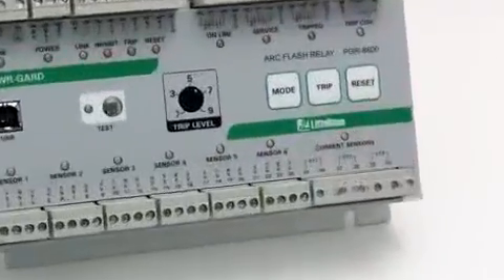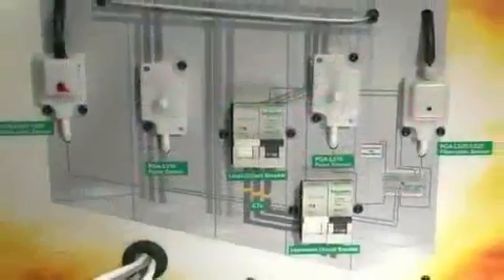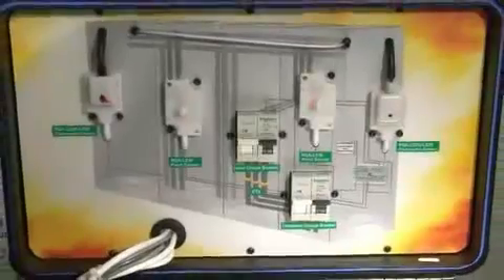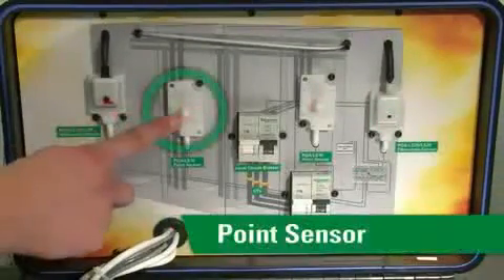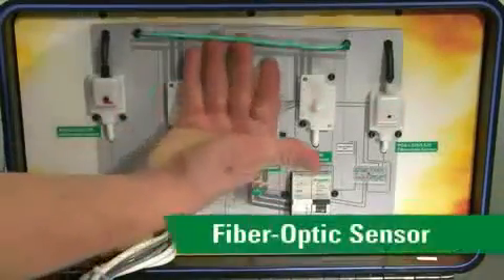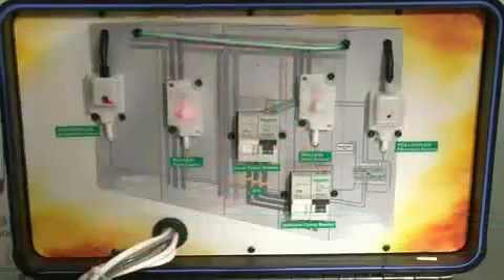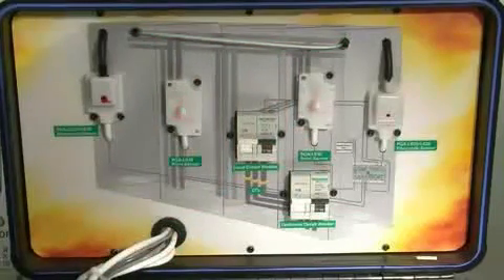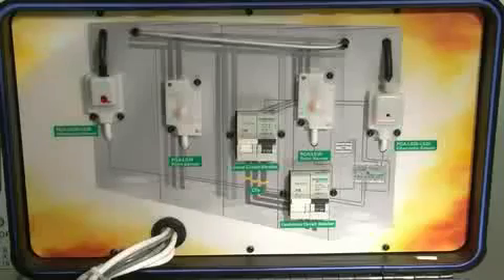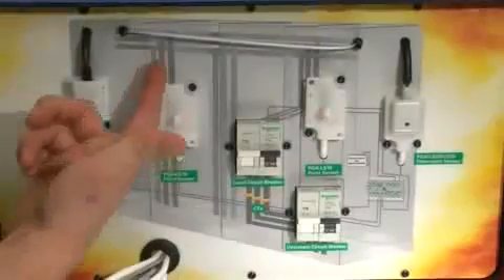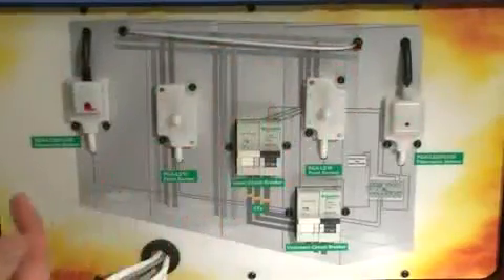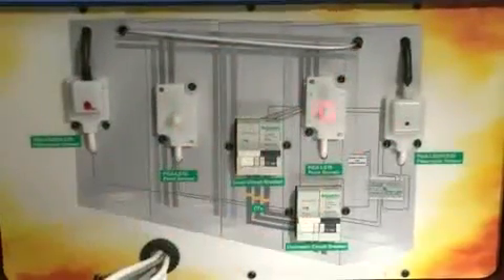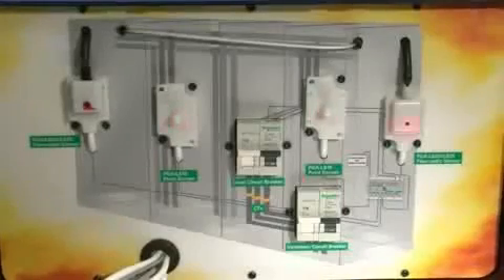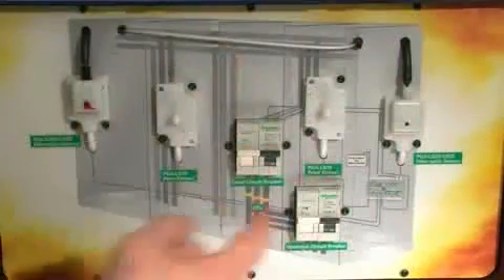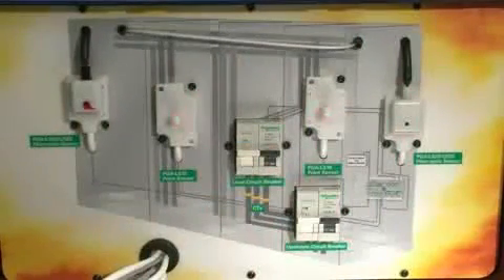The PGR 8800 utilizes two types of sensors to detect arc faults. One is our point sensors that you see here, and the other is a fiber optic sensor, which is actually an 8-meter fiber optic rope, so it's equivalent to around 25 feet. The fiber optic cable can conduct light from end to end. In this example, you only see about 8 inches of the exposed fiber, when in fact you can see an arc flash end to end for the entire 25 feet.